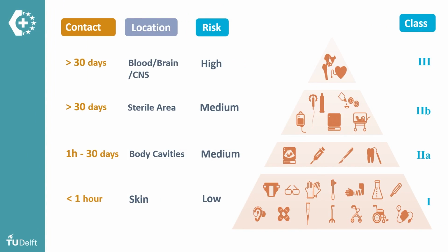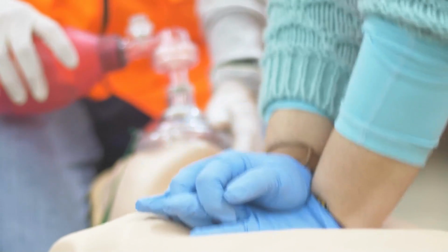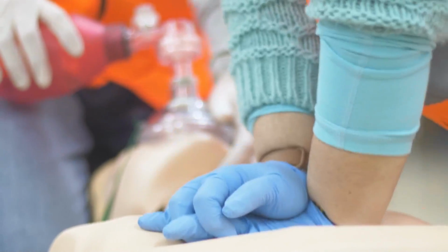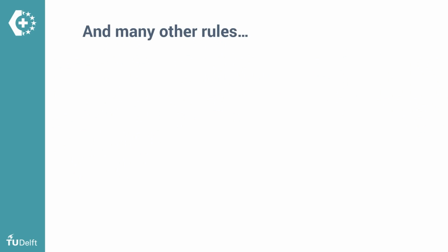But also the duration of the contact is very relevant. Surgical gloves will be on your hand for a brief time, maybe a few hours at most, but a new knee will hopefully be in the patient for many years. And there are many other factors that determine in what class a medical device belongs.